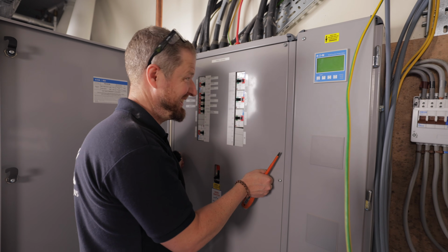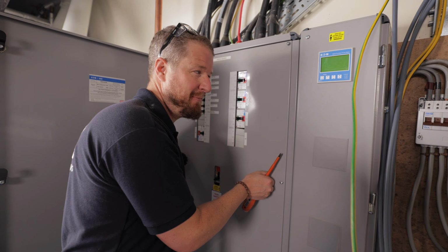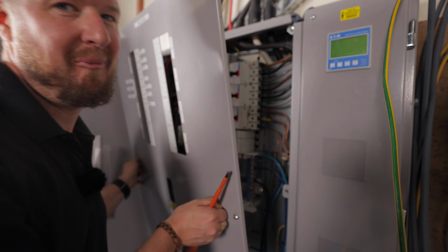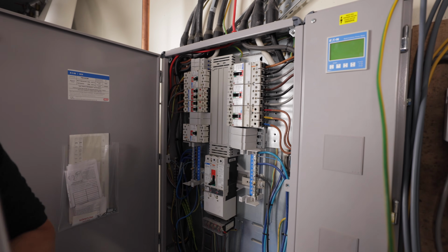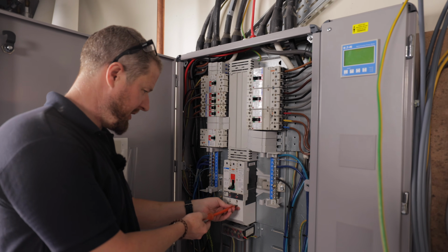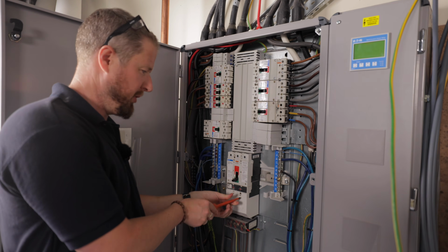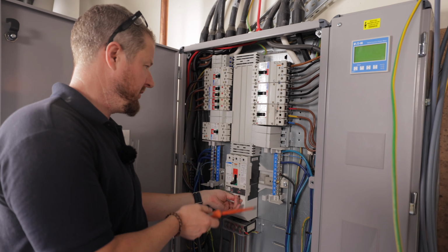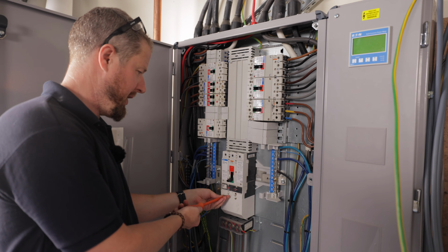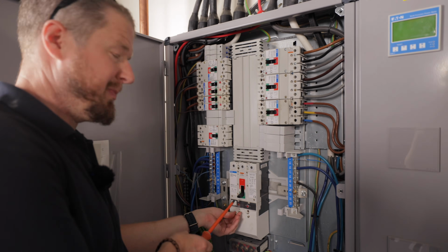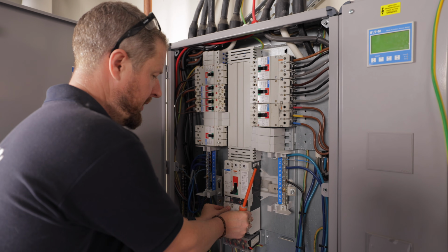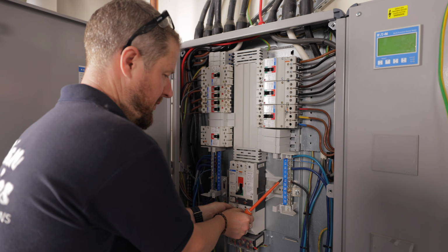Neat or not neat? What do you think? Not bad, not bad. It's fairly spacious as boards go. Now, you might be wondering, why have they got such a big panel board for a house? Because normally you install these type of breakers when you've got a really high prospective fault current and that normal breakers are basically not strong enough.